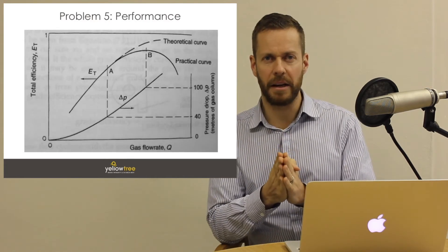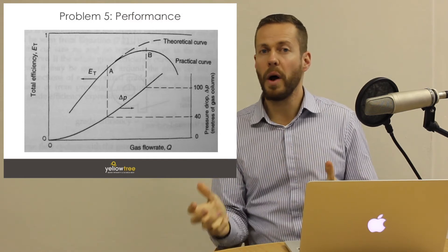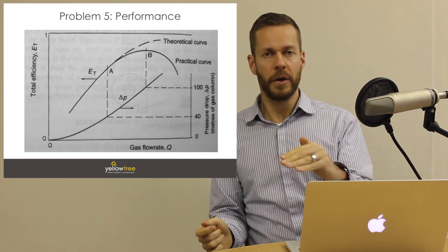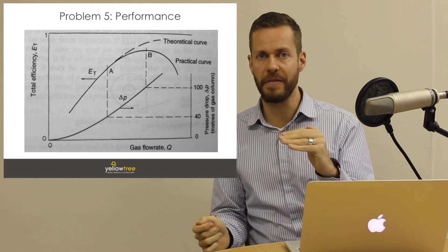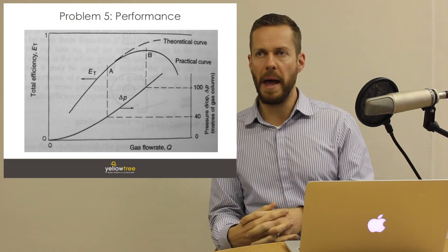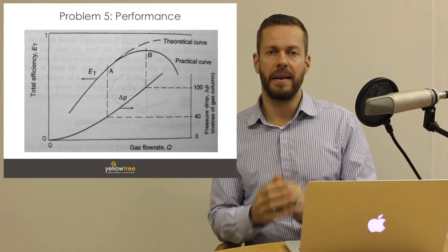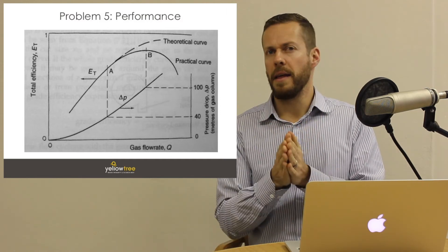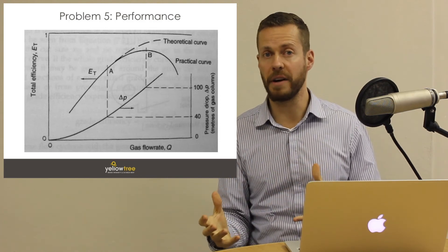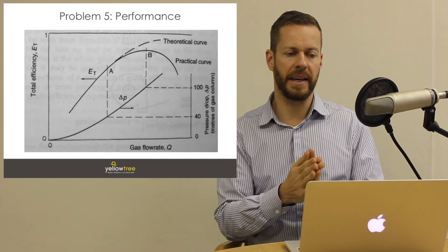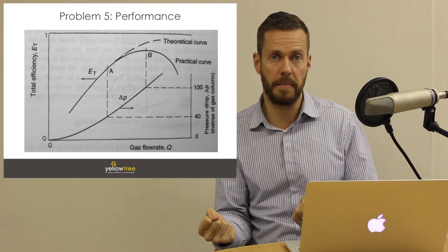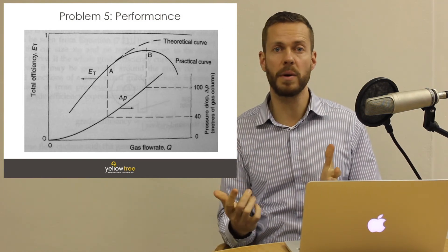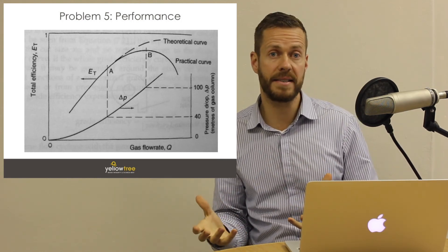The fifth and last problem with multicyclones is that they vary in performance. If you install a multicyclone to reach a legislated limit of 250 milligrams per normal cubic metre, you want consistent performance — not 200 one day and 450 the next. The problem is that multicyclone performance varies as a function of flue gas flow rate. As the graph shows, multicyclones increase in efficiency — arresting more particulate matter — the more flue gas you put through them, because higher flow rate creates stronger centrifugal forces and better separation.